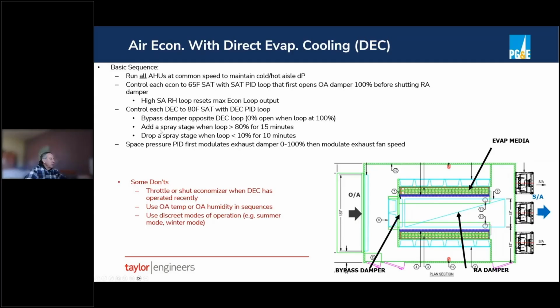stages of spray turned on and off at different conditions. This air handler shows a bank of media here and a bank of media here. These banks were actually split in half, so we had 4 stages, if you will, of direct evap. Those are staged on when the loop gets above a certain amount for a certain amount of time, and you stage on the next stage. And when the loop gets down low, you're overcooling, so you're going to be opening the bypass and then eventually shutting off the stage. So that's how the stages are turned on and off, and the temperature is controlled. The supply air won't always be exactly 80 degrees. It might go down to 78 or up to 82, but that's okay, right? The data center doesn't need exactly 80 degrees.